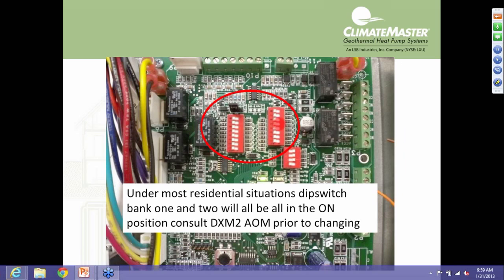For instance, let's talk about a couple of them. Over here on bank number 1, dip switch number 2. If I was to move that into the off position, that is for a commercial option where we have a larger unit with 2 compressors. And then what will happen is, if I move that on a TE or a TZ, I get a call, nothing's going to happen until I get a second stage call, and then it's going to bring on the compressor. So again, that's not something we want to have happen with our residential pieces of equipment that only have 1 compressor. So that dip switch should always remain on in those products.